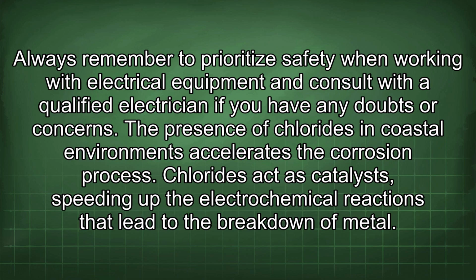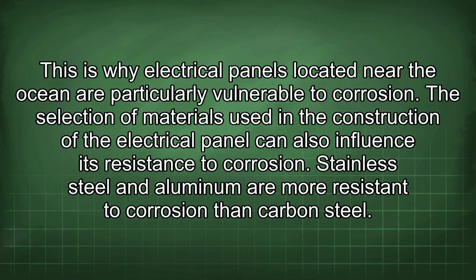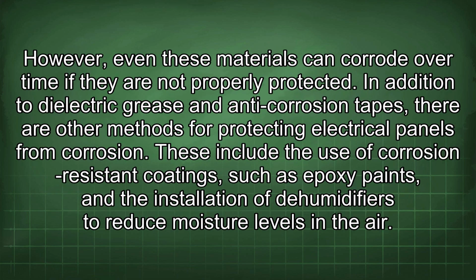Chlorides act as catalysts, speeding up the electrochemical reactions that lead to the breakdown of metal. This is why electrical panels located near the ocean are particularly vulnerable to corrosion. The selection of materials used in the construction of the electrical panel can also influence its resistance to corrosion. Stainless steel and aluminum are more resistant to corrosion than carbon steel. However, even these materials can corrode over time if they are not properly protected.